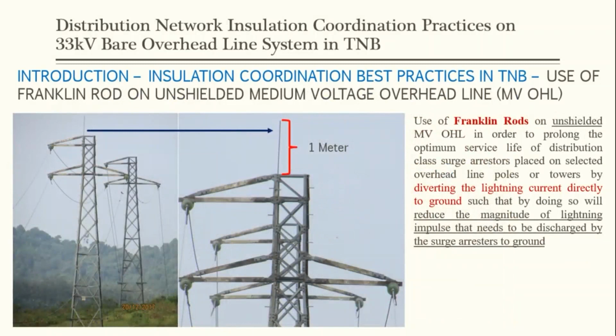Okay. And this will be the simplest form of deviation, or we want to deviate, right? Deviate the lightning strike so it does not strike the conductor, right? So the use of Franklin rods on unshielded medium voltage overhead line in order to prolong the optimal service life of distribution class surge arresters placed on selected overhead line poles or towers by diverting the lightning current directly to ground, such that by doing so will reduce the magnitude of lightning impulse that needs to be discharged by the surge arresters to ground. Okay, so we try to divert or deviate, like the first part I was talking about.